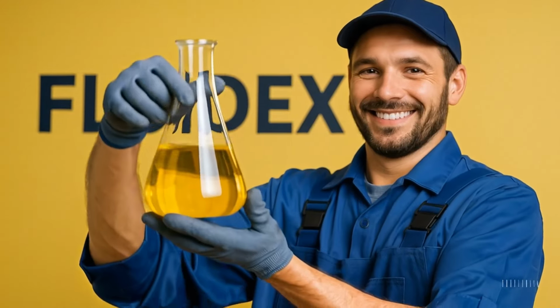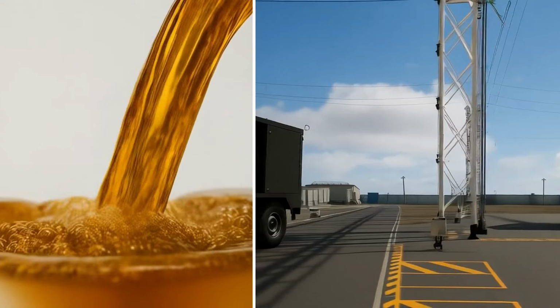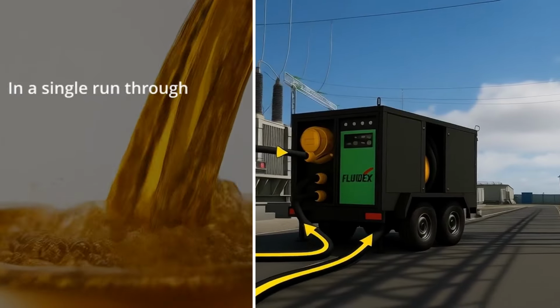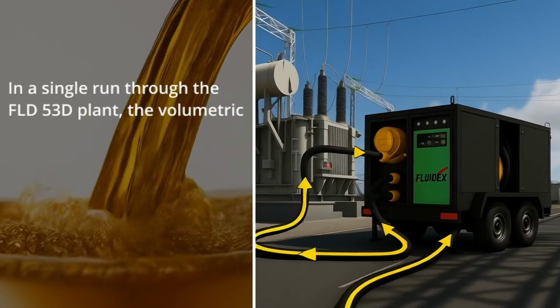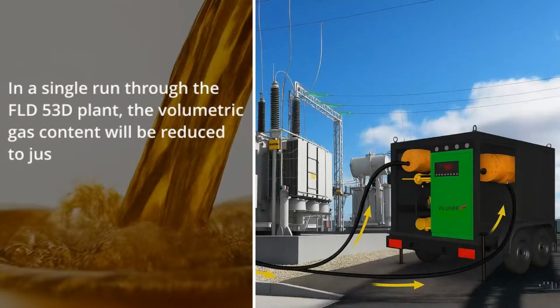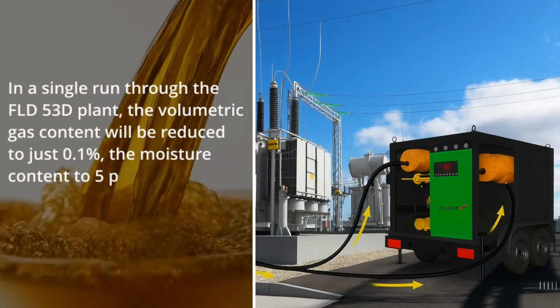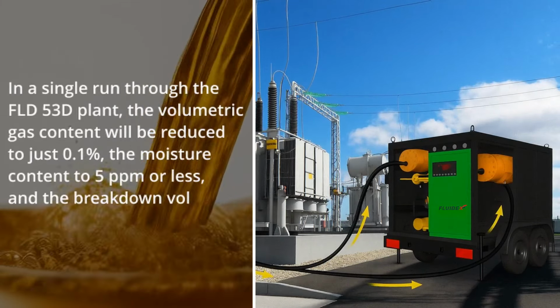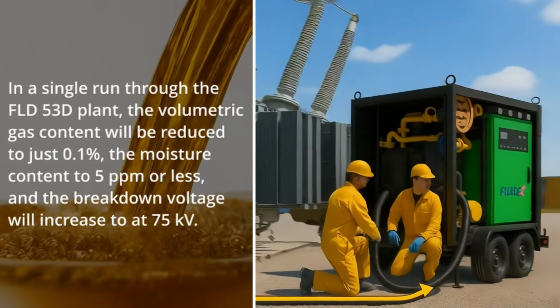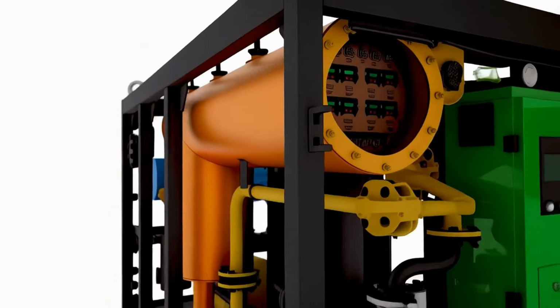Secondly, it delivers high quality oil processing. In a single run through the FLD 53D plant, the volumetric gas content will be reduced to just 0.1%, the moisture content to 5 ppm or less, and the breakdown voltage will increase to at least 75 kilovolts.